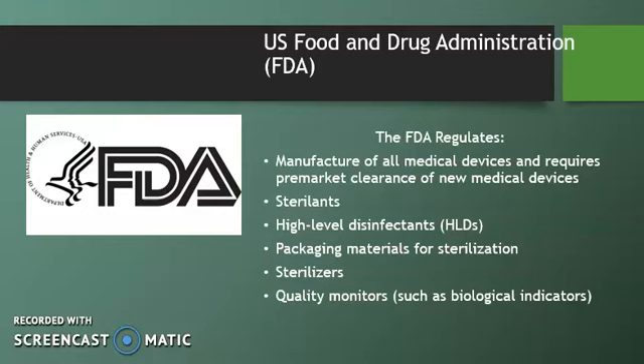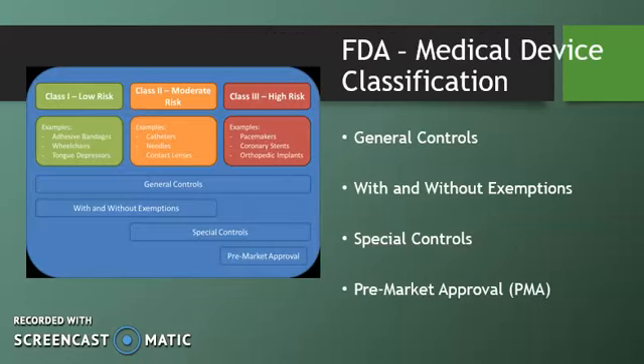The FDA and other agencies such as the Centers for Disease Control and Prevention and the Centers for Medicare and Medicaid Services function within the Public Health Service of the U.S. Department of Health and Human Services. The FDA medical device classification describes the level of regulation placed on any device; this depends on how the FDA classifies the device. Class 1 devices include low-risk devices such as handheld surgical instruments and ultrasonic cleaners. Class 1 devices are subject to general controls and are exempt from pre-market approval.